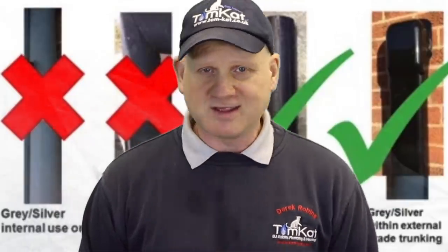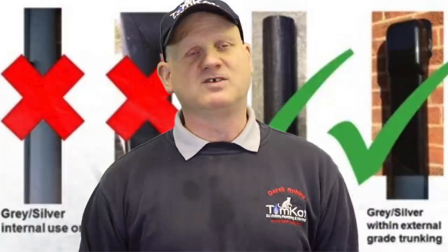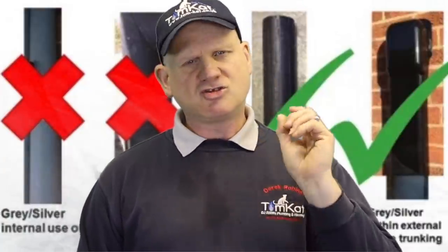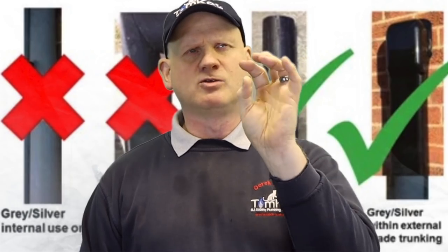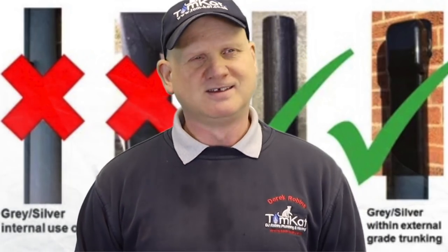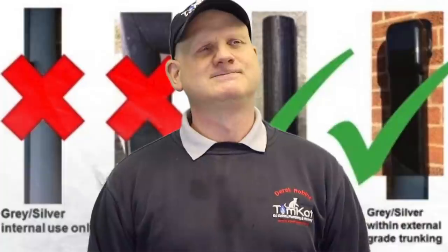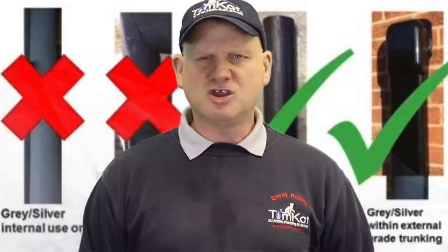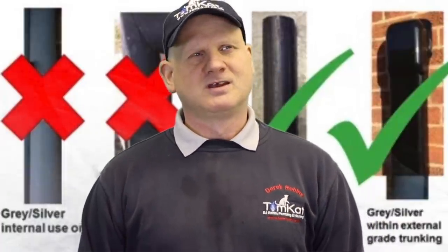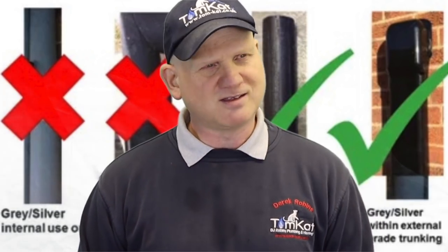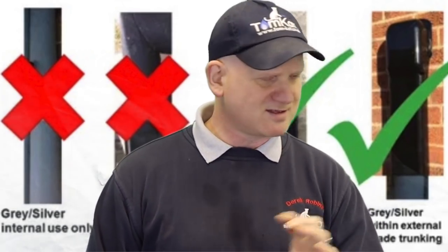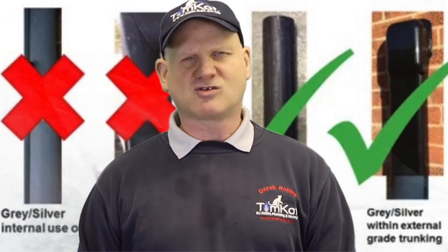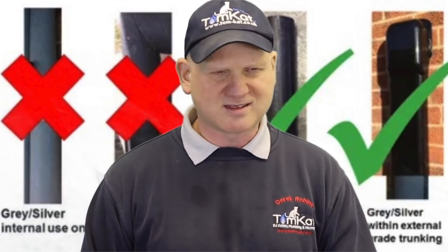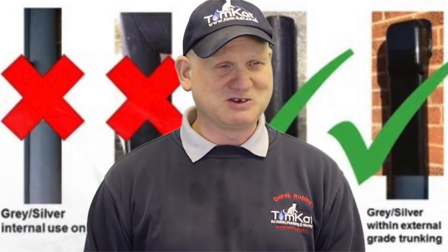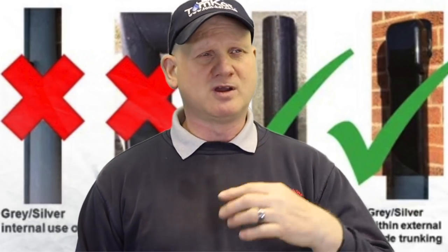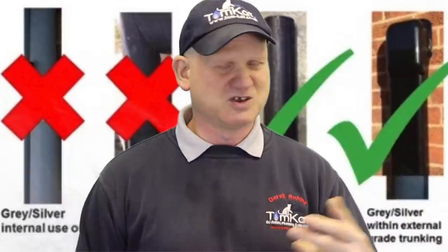Now let's talk about this insulation which I mentioned at the beginning of this video. A lot of engineers use this Class O nitrile rubber insulation, I think that's how you say it. But there's a couple of problems with that. First of all, it's not UV protected. So you've got to protect it, and you've got to use a special paint to paint on it, and you have to do it twice within a few weeks. You have to follow the manufacturer's instructions with it, but it stops the rubber cracking and turning to dust.